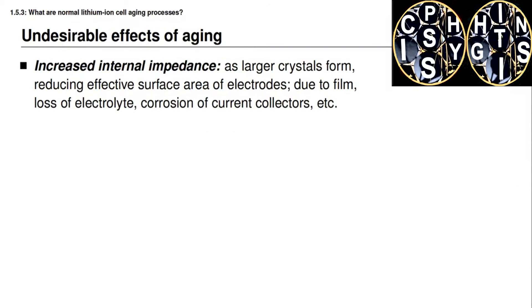It's helpful to understand why cells age and degrade and why they don't last forever. One net result of any of these aging mechanisms is increased internal impedance. As larger crystals form, the effective surface area of the electrode is reduced, increasing impedance. When films form on electrode particles, it's harder for ions to get in and out, so impedance increases. When electrolyte is lost or current collectors are corroded, it makes it harder for electrons or ions to move, resulting in increased impedance or resistance.